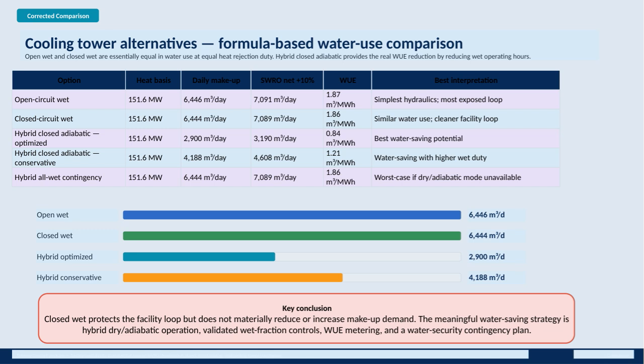The real water savings come from hybrid closed adiabatic systems. When optimized, these systems cut the daily makeup water demand down to about 2,900 cubic meters, with much improved WUE of 0.84. Even under more conservative operating conditions, hybrid systems still outperform traditional wet towers, using roughly 4,188 cubic meters daily and achieving a WUE of 1.21. This shows how important incorporating dry or adiabatic operation modes is for reducing water use.